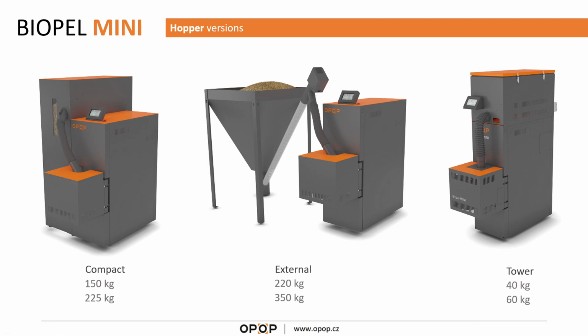Of course, the tower hopper is small, so the advantage of this version is that you can have a small boiler which can fit easily into almost any boiler room. The width of the boiler, this diameter, starts from, I think, 36 centimeters. So the width of the boiler is only 36 centimeters, so you can fit it almost anywhere. But the downside is that you have a smaller pellet hopper. But if the boiler is installed in new houses or houses that are renovated and with good insulation, I think it should last for 1 day with no problem. So you have to fill it each day. Okay.